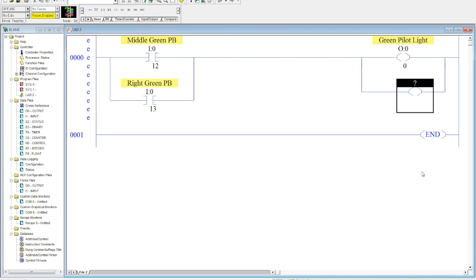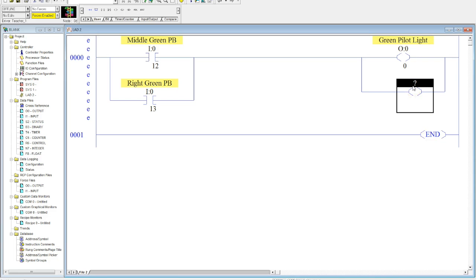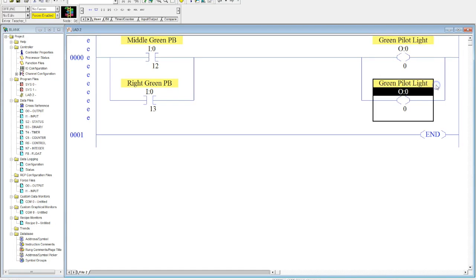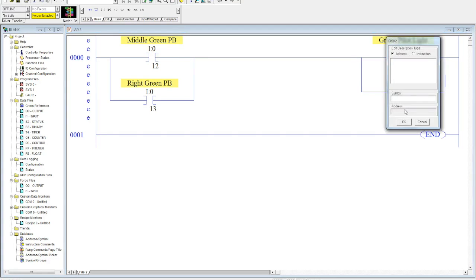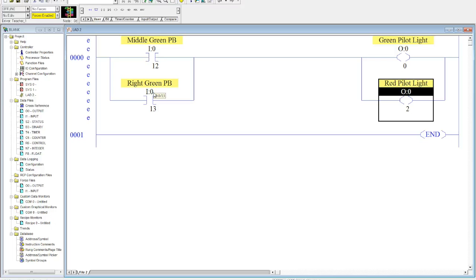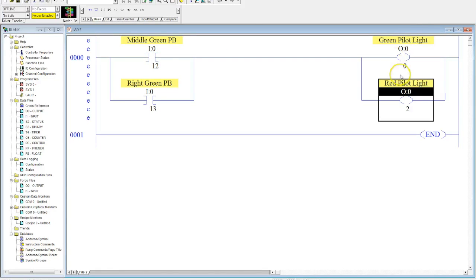Now, let's say that I want to do the red light. So, I want to have the red light and the green light on at the same time, which is what this program will do. What I can do here is, if I don't want to type in the full address here, I can actually drag this output address right down to here, click on the bottom, and change it to 2, which was my red pilot light. Select OK, and there we go. Now, we have our two green push buttons in parallel, and we have our green and our red light in parallel. And if I were to download this now, I could activate either push button and activate both of these outputs.